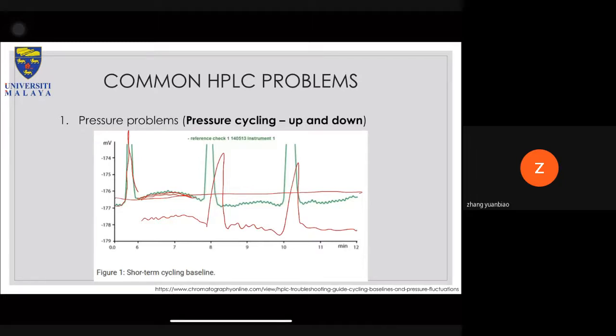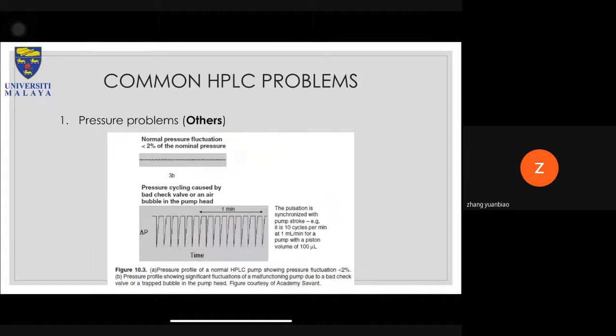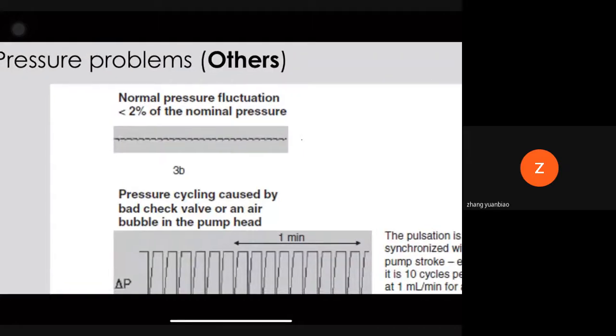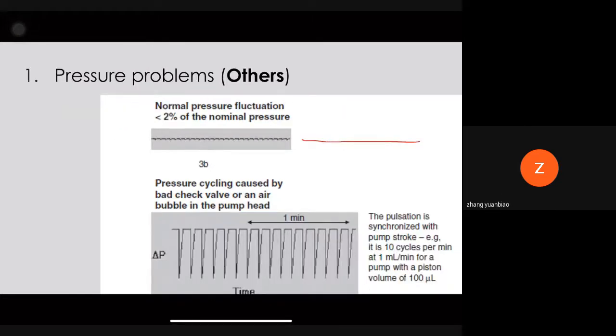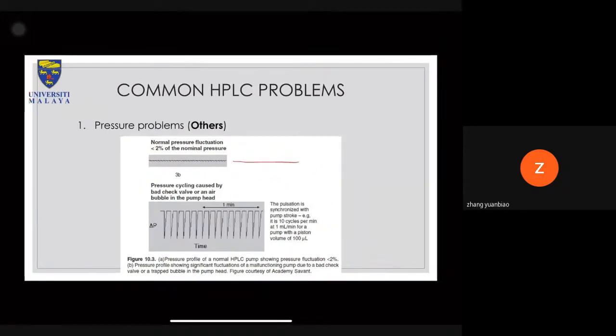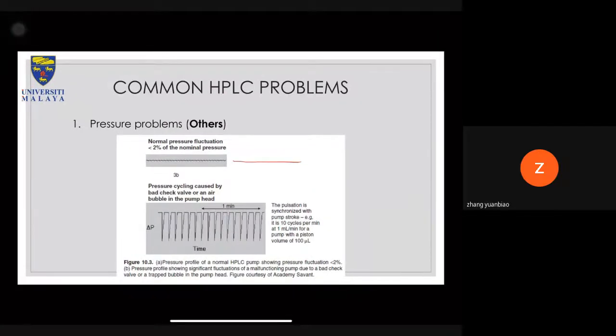All right, so some other problems that you might encounter that are related to pressure: normal pressure fluctuation is less than 2% of the nominal pressure. Even if you see that it's not flat, normally it's very flat. Something like this is an indicator that in the near future something is going to happen that stops you from doing whatever you are doing.